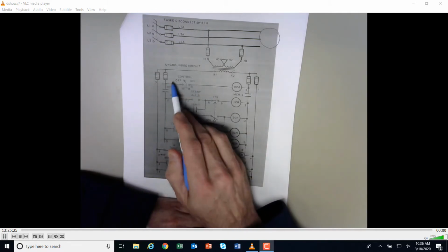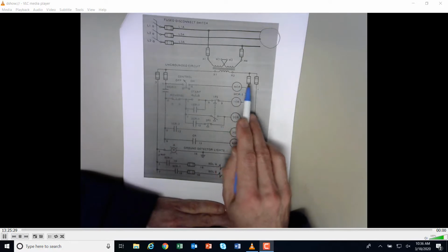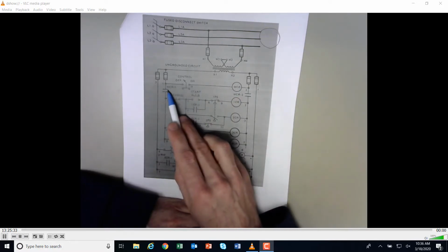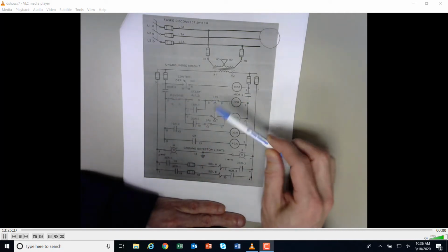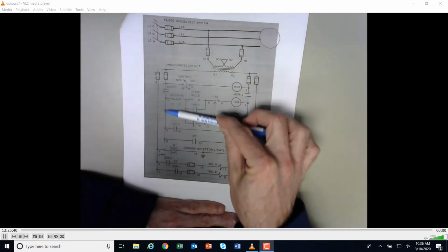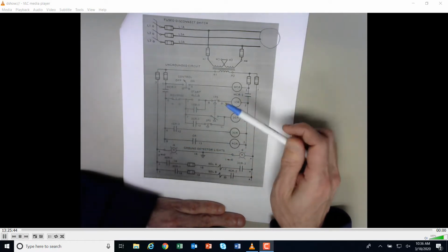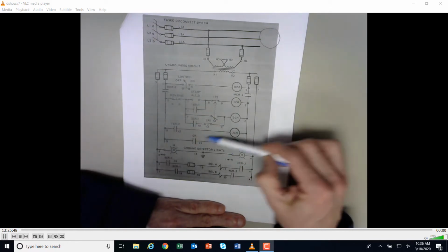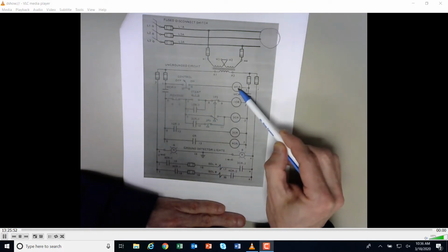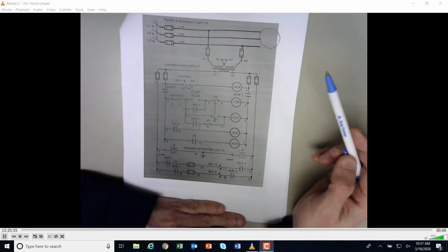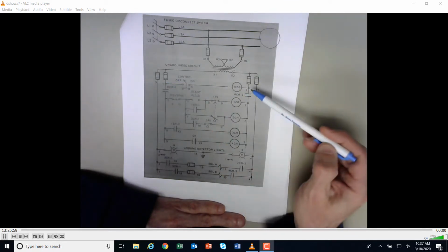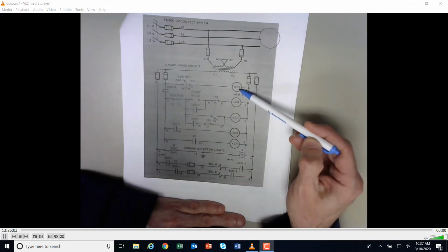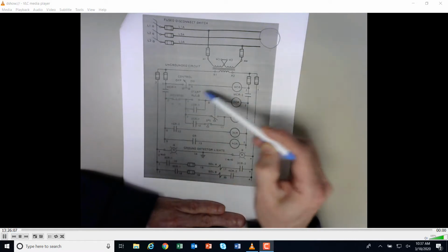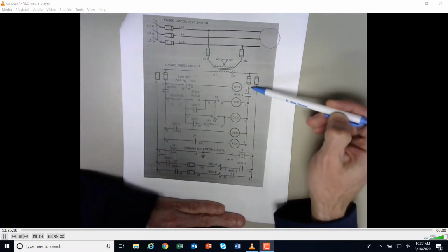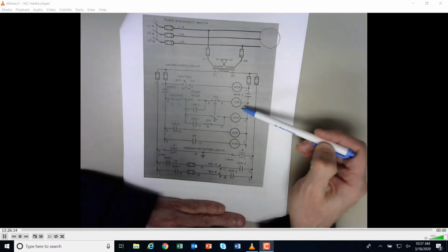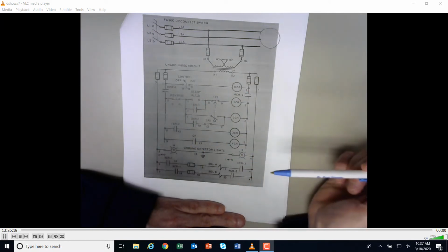So let's just start to look at this master control relay. This master control relay is on a fuse, and it's a selector switch here. So when the MCR goes on, what that does is that closes these contacts here, and now this part of my control circuit is going to be working. So now I've got my logic here for my switches and my holdings and starts and reverses and everything, but this won't work unless I turn on the master control relay. A lot of times the master control relay is on memory as well in case there's a dropout. But if for some reason one of these fuses blew, well then the master control relay is going to go down, which means that this is going to open up, and not only would I not get any voltage on these rails here, but because this opens, it's like a double kill. This whole control will go down, okay?